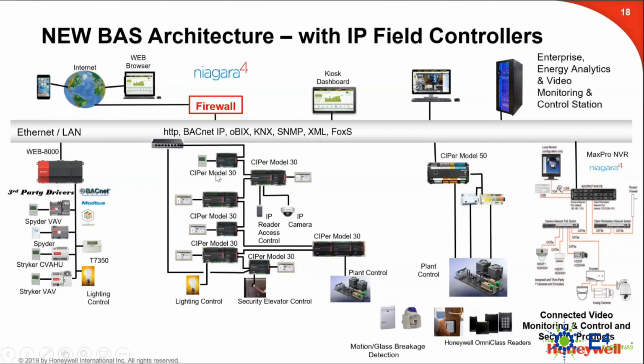But if I can focus your attention to the middle of the screen, this is where we're seeing a transformation in the digital technologies impacting this conversation. What we're doing now is taking these field controllers that have historically been robust, tried and true, but operating on a slow network. This was historically a BACnet network running at 76,800 bits per second, relatively slow - technology from the late 1980s.